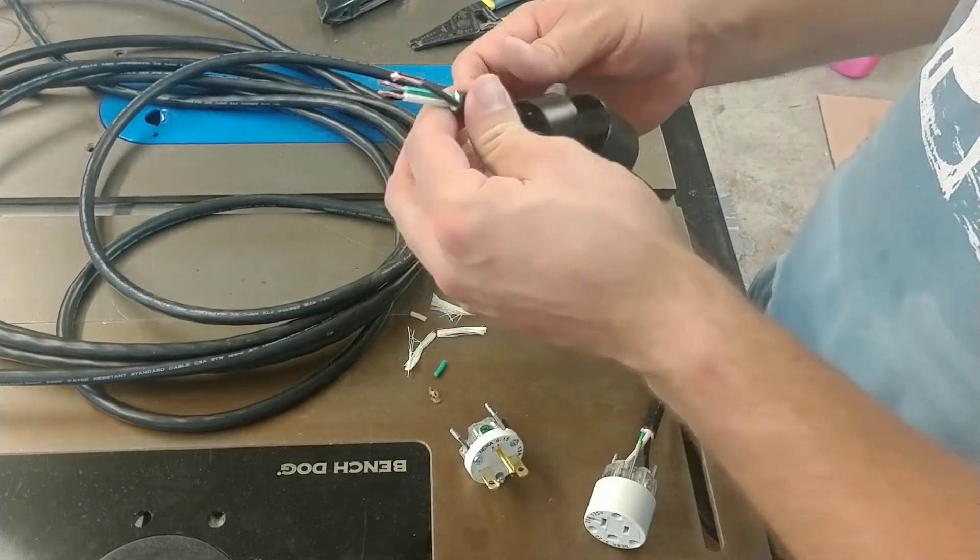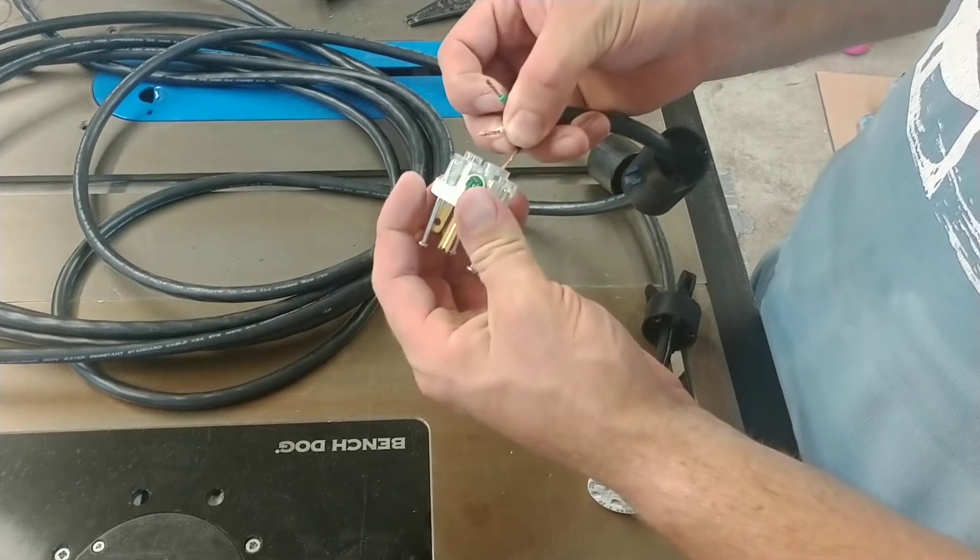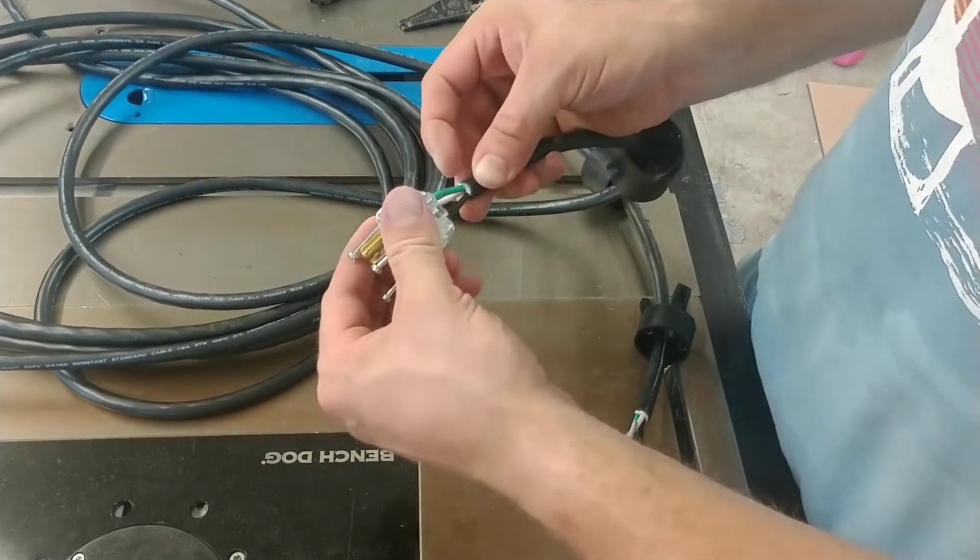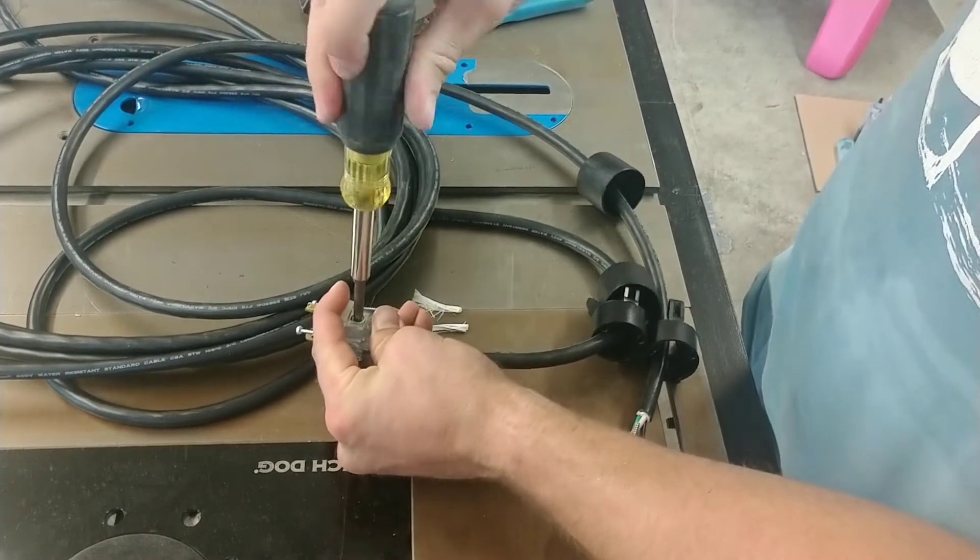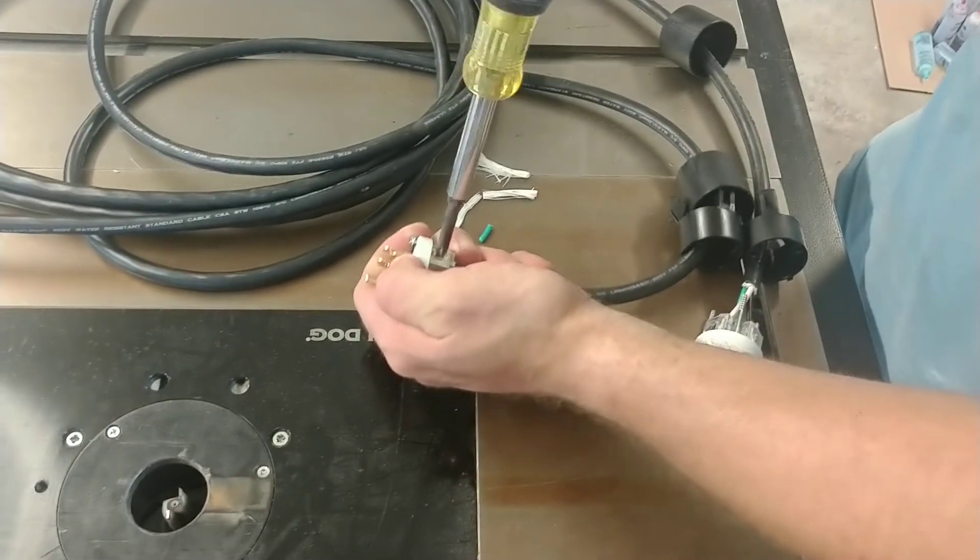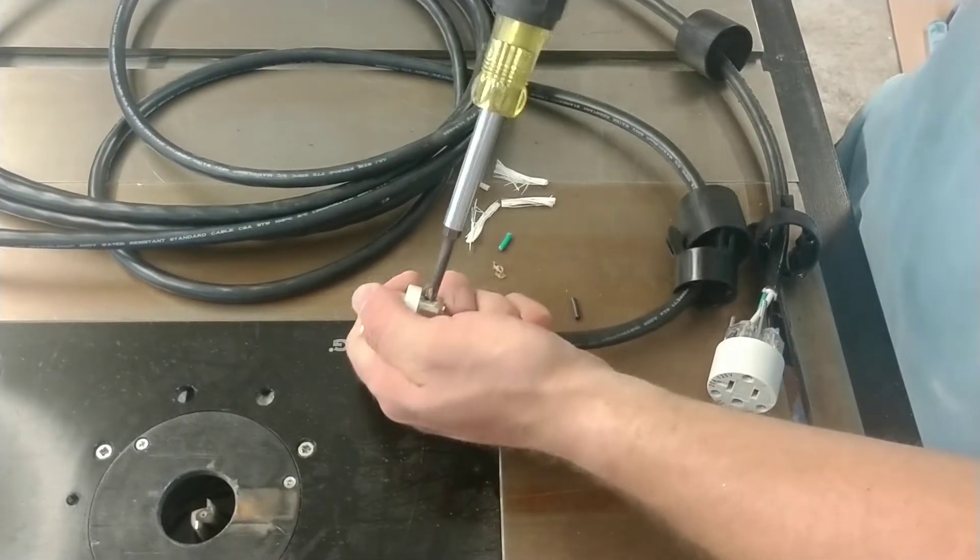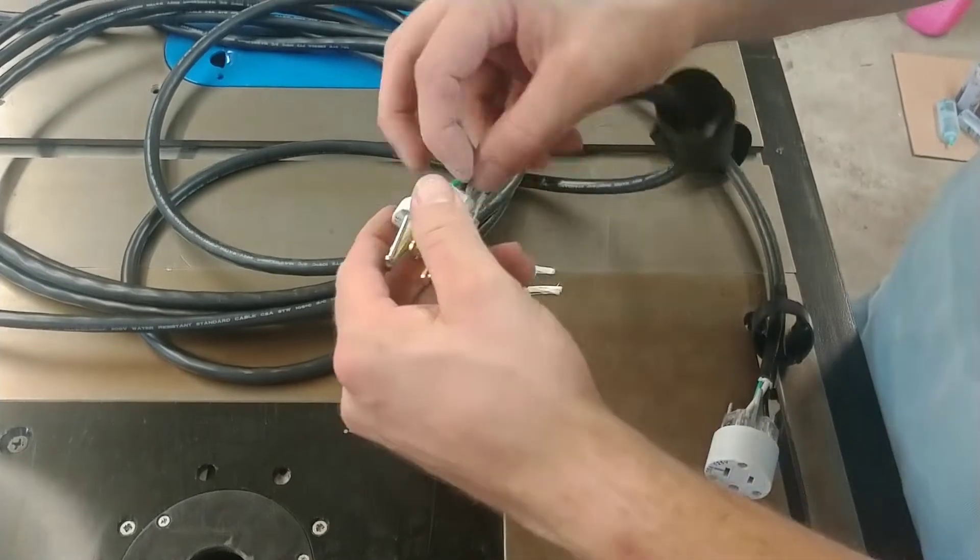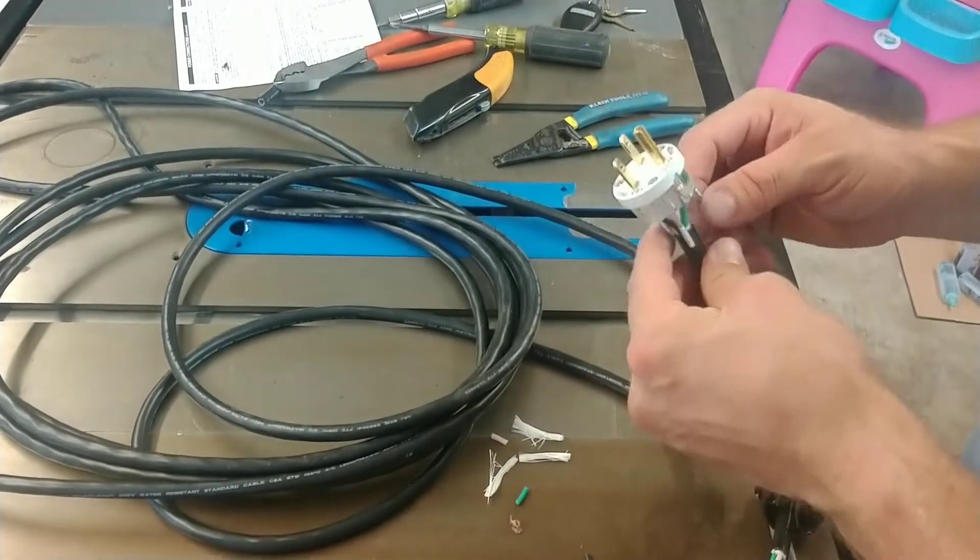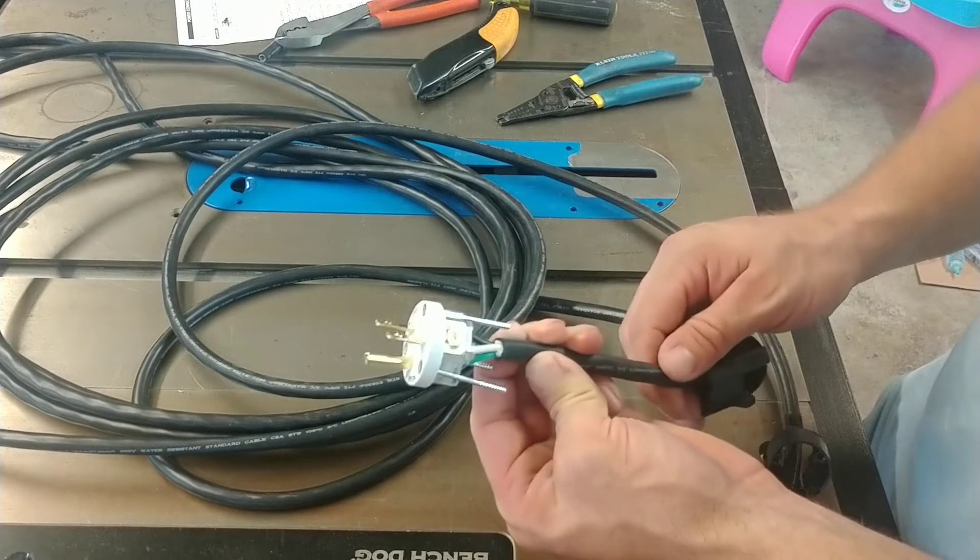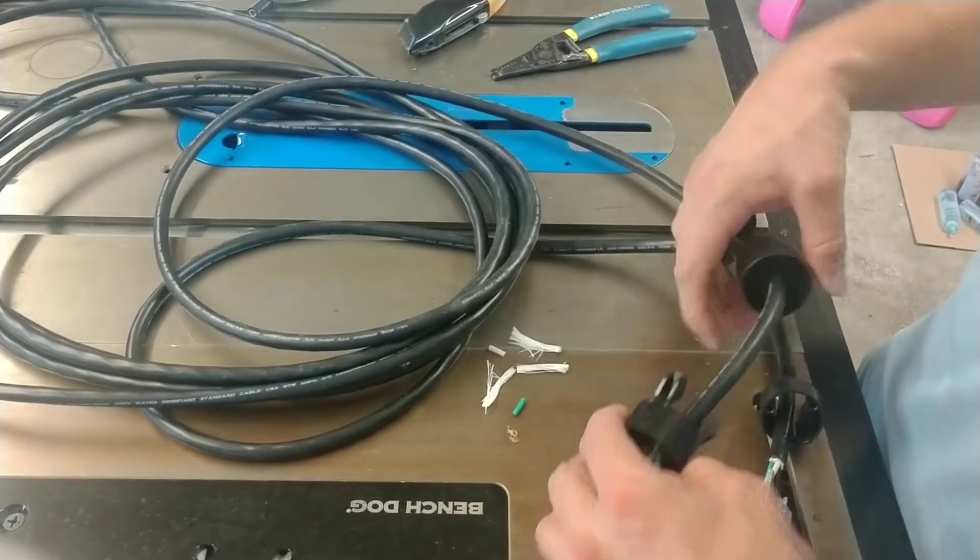Feed this one through there. Just shove one of these in each one of those. Like I said, make sure that the ground gets in the green one. Just tighten them up real good. Got it good and tight. Give each wire a little tug to make sure it doesn't back out at all. Like I said, with the phase rotation, it is possible that the saw blade may run backwards. It shouldn't because this is only a 240, it's not like a three phase. But if it does, swap the two. That should take care of that problem.